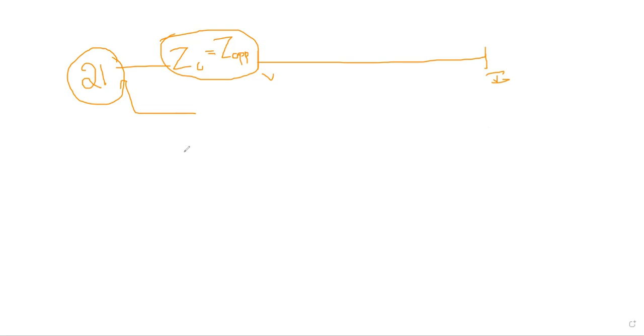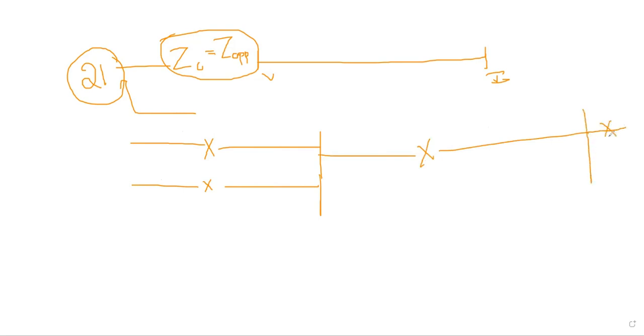But again, what is the case? Suppose I have a relay here. I have a feeder, a line here, and one more line, and one more line, and this is the breaker line. Suppose a fault occurred here, take F1. Let's assume this is a 400 kV system. Let's assume the impedance of this line is 10 ohms, this is 10 ohms, and the impedance of the other line is 4 ohms. Now, when you are implementing the distance protection, this is the A substation and this is the B substation. These are the two lines going out, and from B one more line going out. So all this has to be coordinated.